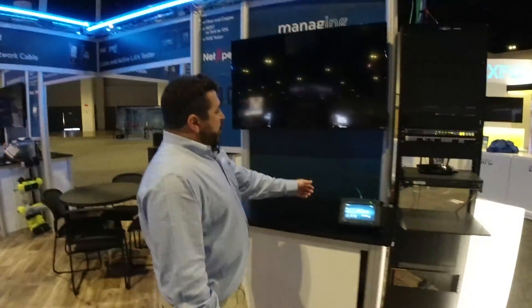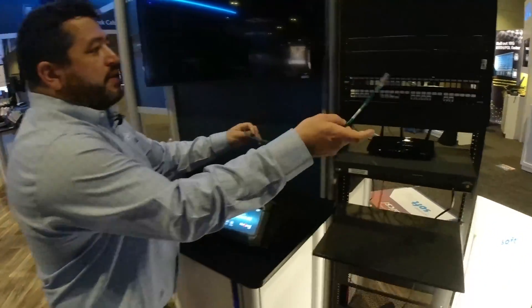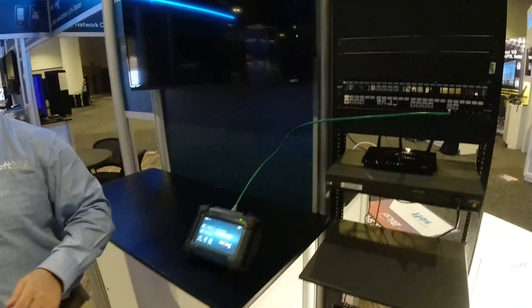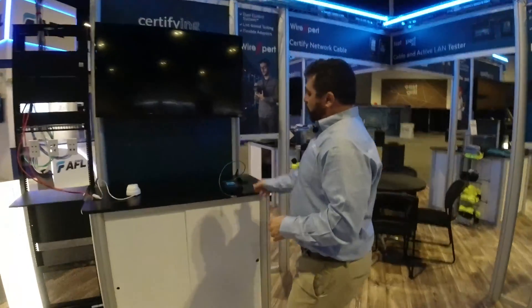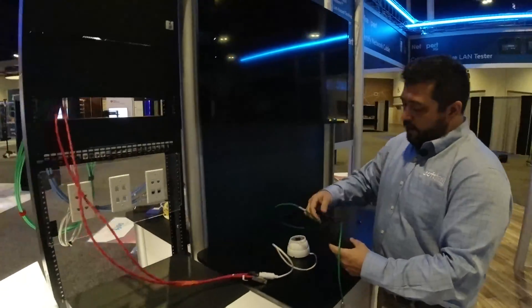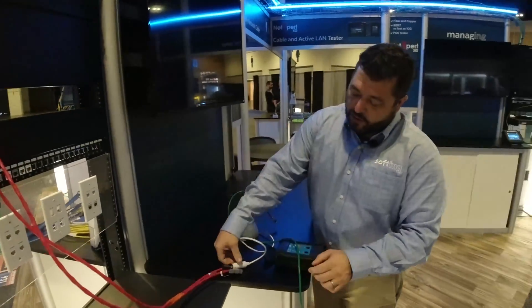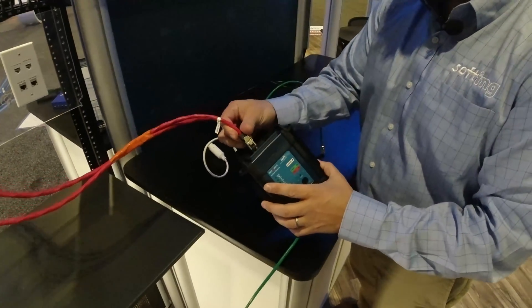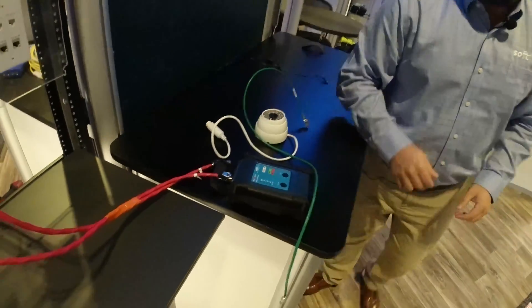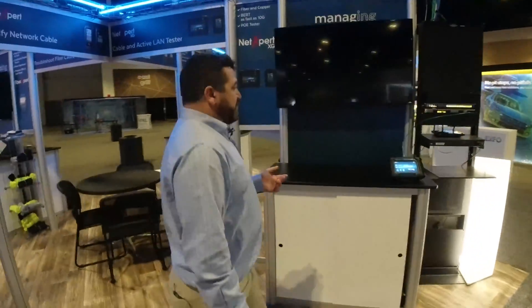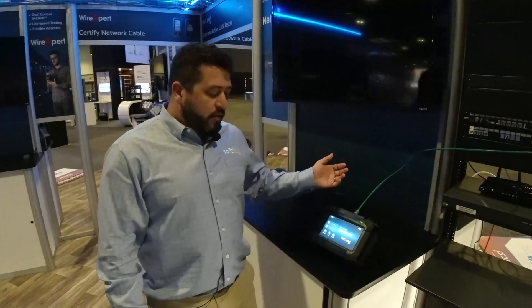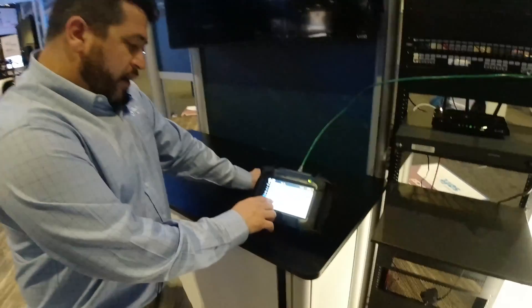Let's go ahead and connect over here. This is the patch panel side of these MPTL links. Over on the camera side, we'll simply pull the mod plug out of this cable run and go directly into the remote end. And let's go back to the tester — we don't have to look for the standard, we don't have to look for anything like that. We simply pull up a list and test.